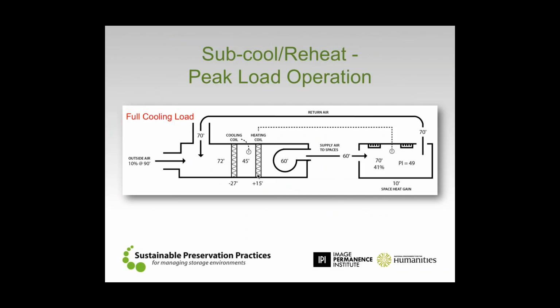We talked about, just a couple of minutes ago, how these systems are designed for peak operation. And this is sort of normal operation for a mechanical system that's going to subcool and reheat on a peak day. Now, it's 90 degrees outside. Here we are over here at the outside air. And we're bringing in 10% of that total volume and blending it here with 70 degrees of return air. So in order to take that mixed air condition and get it down to our dew point that we need out in the space, we're going to do 27 degrees worth of work here at the cooling coil. We're going to drop that temp by 27 degrees. And over here at the heating coil, we're going to heat it back up by 15 degrees in order to get the right supply air condition to send out to the space and achieve that particular preservation goal.